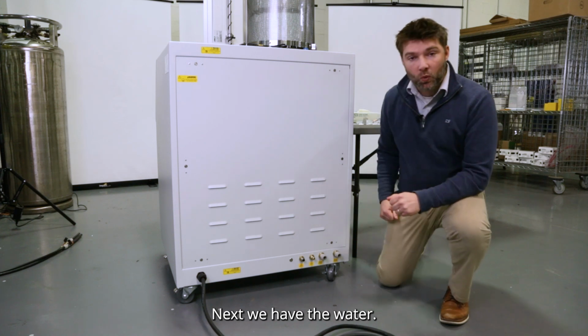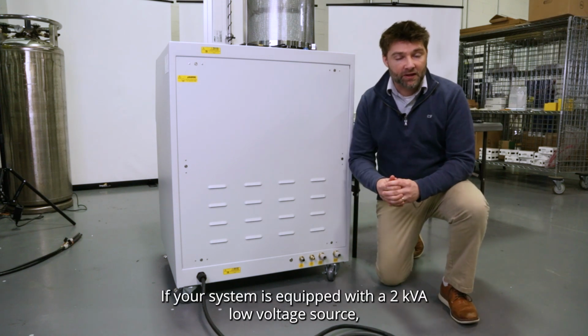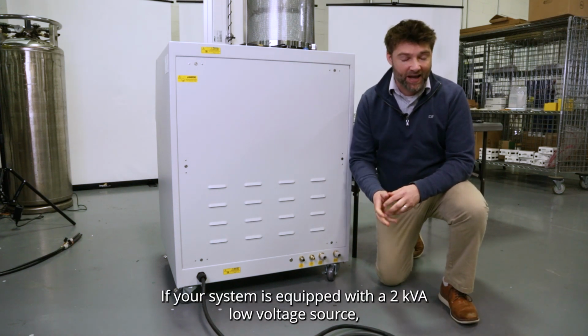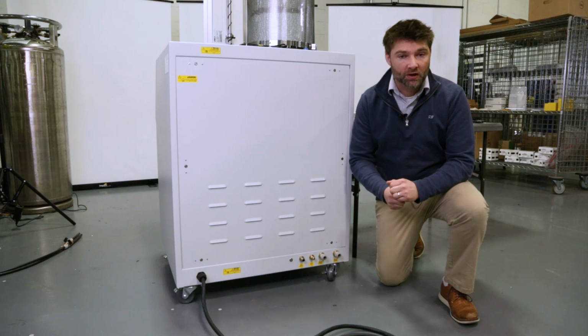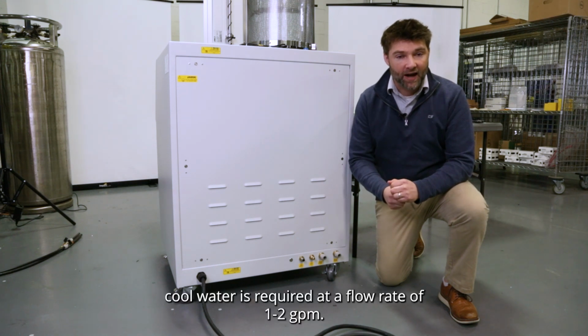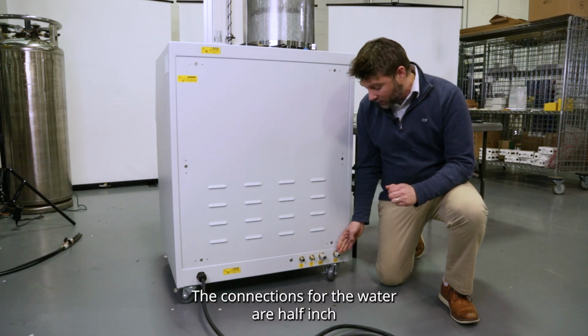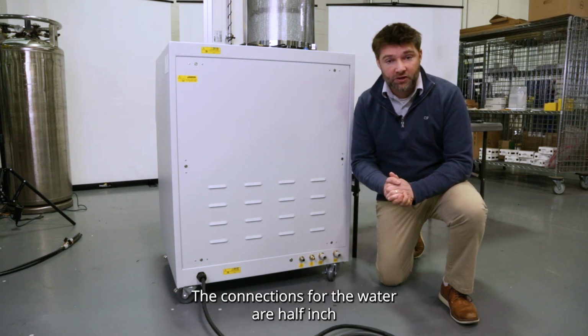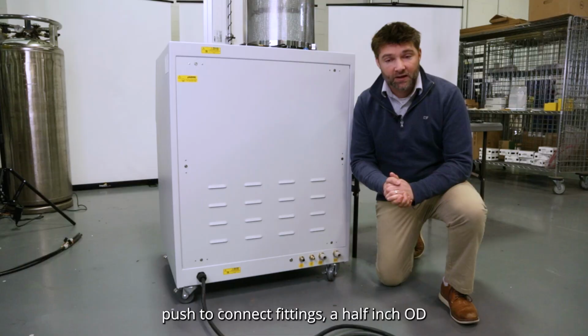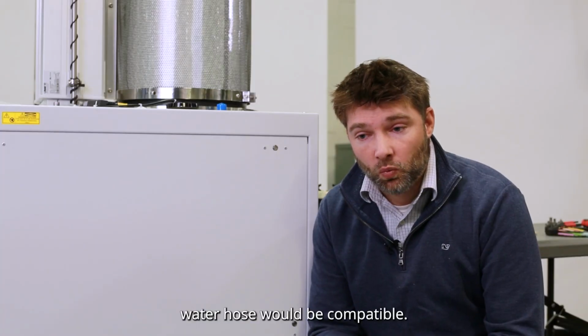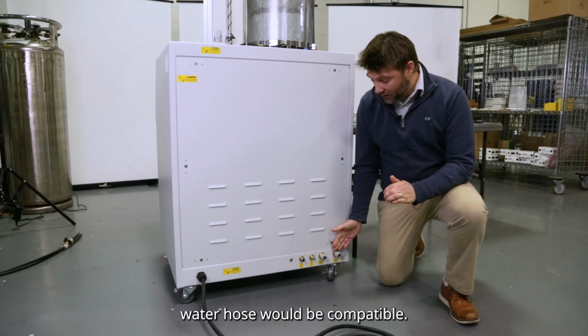Next, we have the water. If your system is equipped with a 2 kVA low voltage source, coolant water is required at a flow rate of 1 to 2 GPM. The connections for the water are 1/2-inch push-to-connect fittings. A 1/2-inch OD water hose would be compatible.